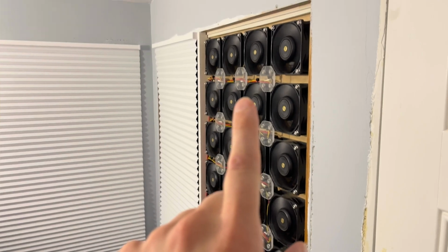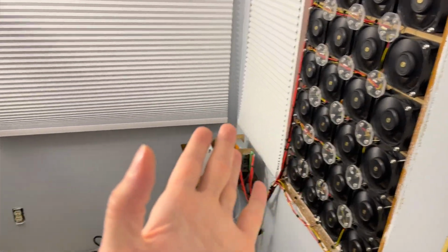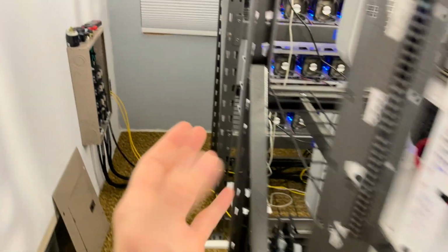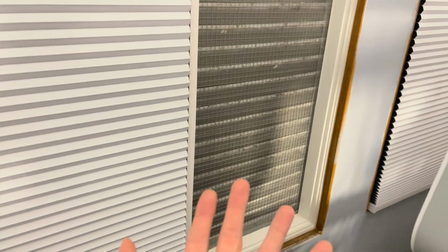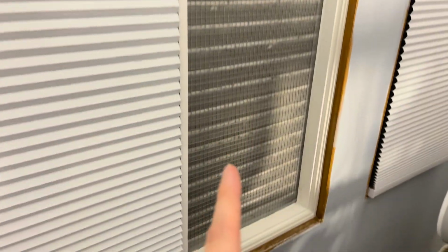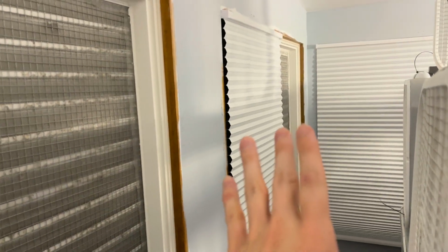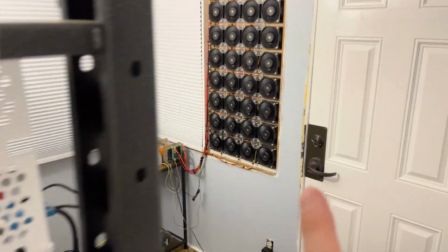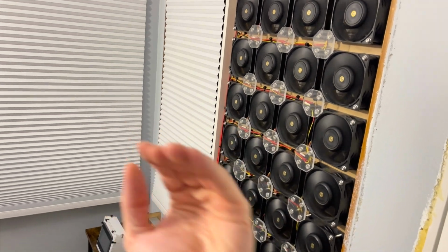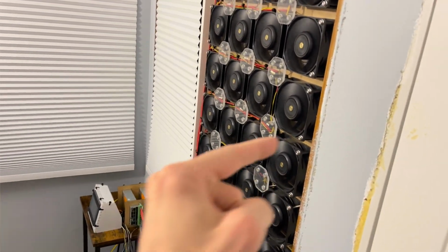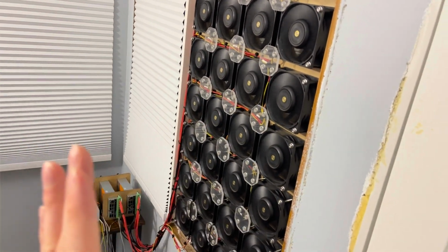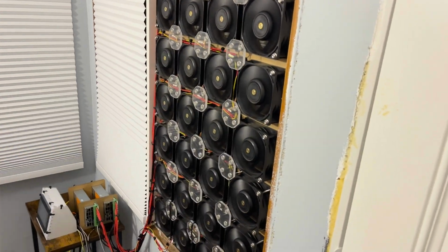That's trouble. And now, in my environment here, for example, these fans running at full speed, because the static pressure will depend on speed, the more air you try to pull through an opening, the more resistance it'll face. But you can see, here's the intakes here, right? Same size intakes, there's two of them. And the exhaust is the same size. And there's louvers on the other side, so it's like an angled aluminum shutter thing. So these fans have resistance on that side as well as this side. They need to push air into angled slats.